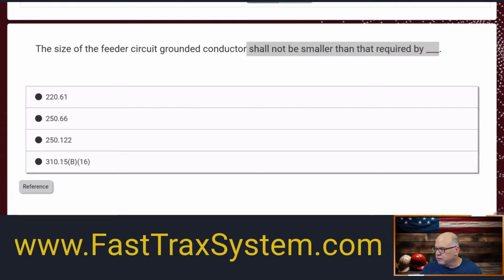So you're thinking, okay, well, which one do I need to use? Okay, so remember, key thing here, it says the size of the feeder circuit grounded conductor shall not be smaller than required by, okay? So we're talking about the grounded conductor. Now, could be larger based on a load calc or whatever, but this is just the general statement. You're thinking, well, where do I find this information? Well, first of all, it's talking about a feeder.